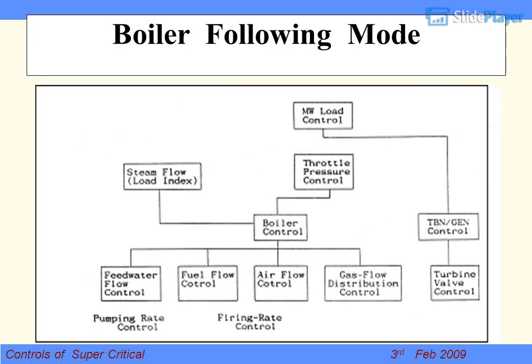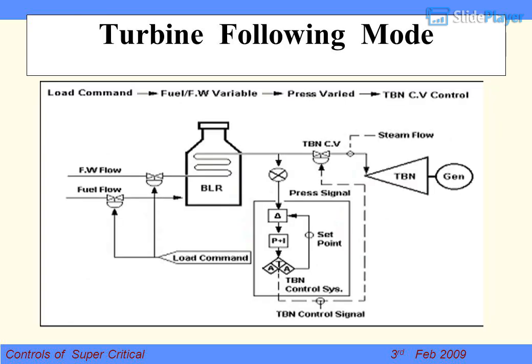Now we have to meet the load demand, so we can follow certain strategies. There are different modes. In Boiler Following mode, whenever generation load is increased, the turbine CV will open first, then pressure will drop, so feed water and fuel have to increase to meet MW demand. Load following capacity will be fast in this case. In Turbine Following mode, whenever load is increased, the load demand is given first to increase fuel and feed water, then based on pressure change, load will be changed, so load following will be slow.